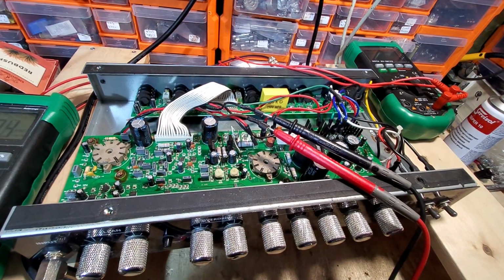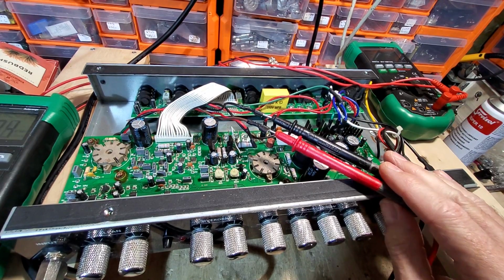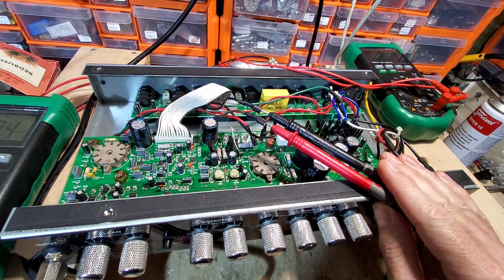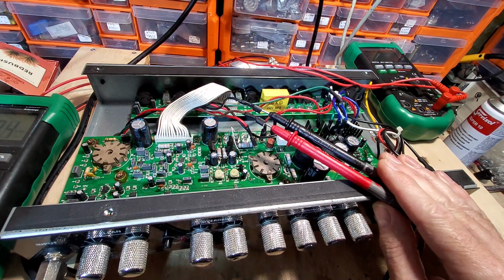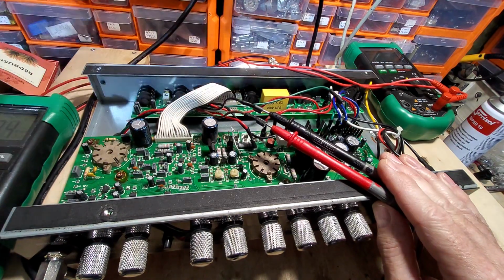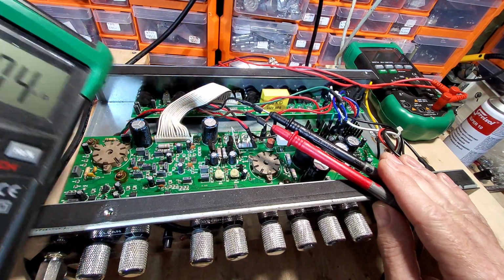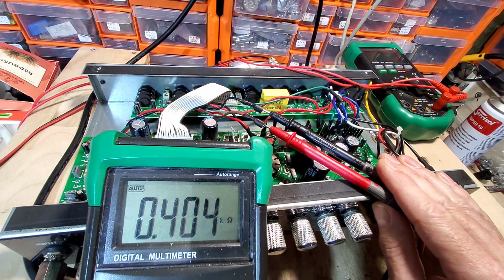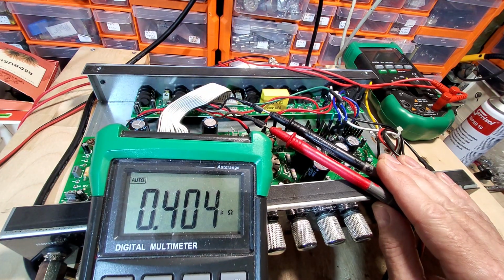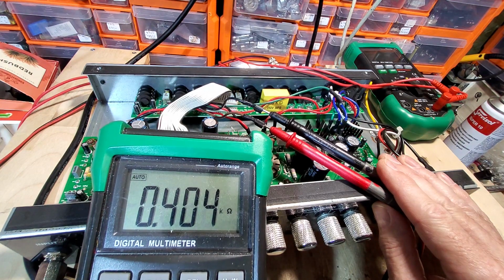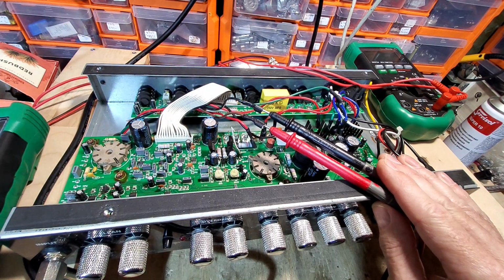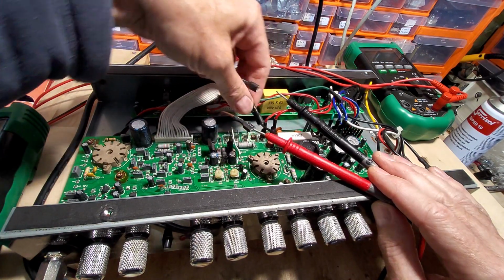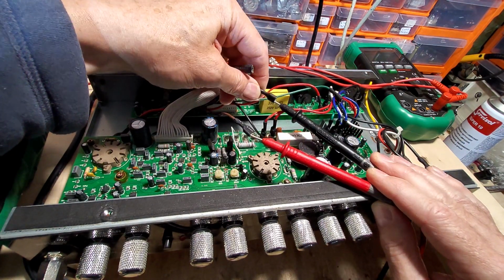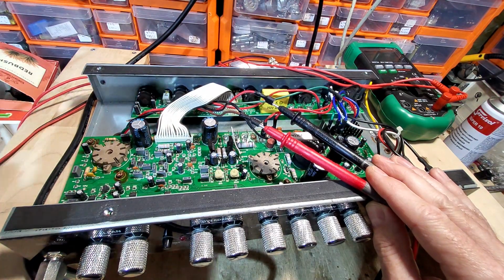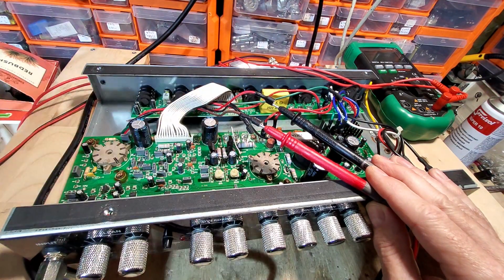I've just done an impedance test on this primary winding of this output transformer, and it turns out that brown is center tap and not red, according to that. So just shows you should never go by the colours. So 404 ohms we've got there on that one. So now if we go brown and red on there, you see we've got 482 ohms.